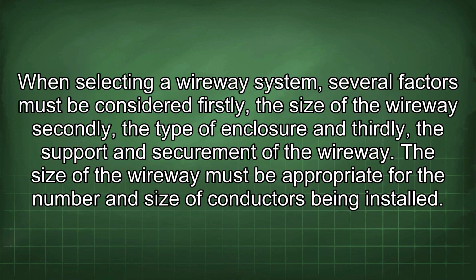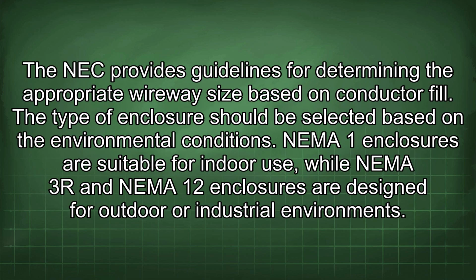When selecting a wireway system, several factors must be considered. Firstly, the size of the wireway. Secondly, the type of enclosure. And thirdly, the support and securement of the wireway. The size of the wireway must be appropriate for the number and size of conductors being installed. The NEC provides guidelines for determining the appropriate wireway size based on conductor fill.